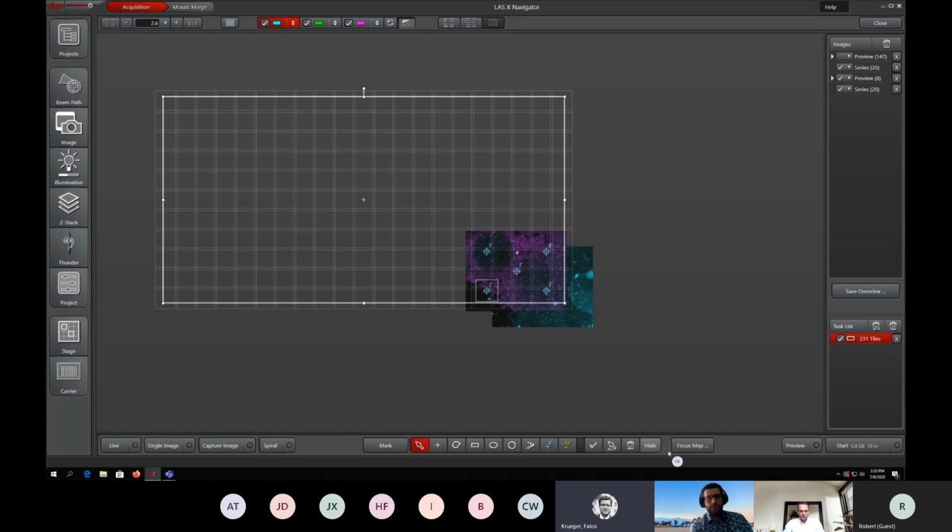And it also depends on your sample quality in the end. Also, this laminated one was very wavy. So the distribution of focus map points is then up to you. If you have an overview scan, it makes sense to follow certain areas. When you see there's a certain wave, you can set there more focus points.